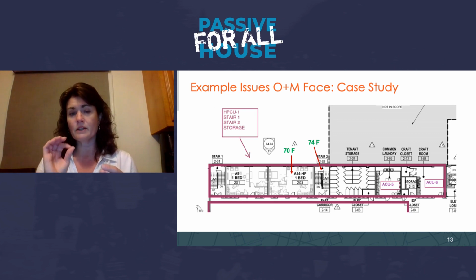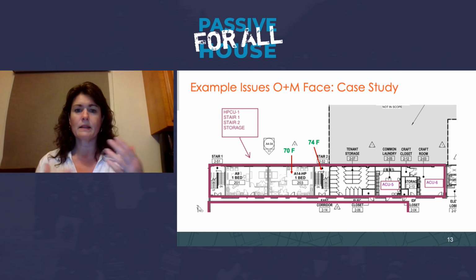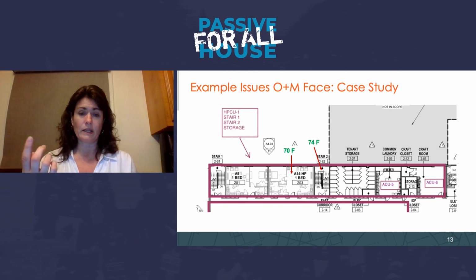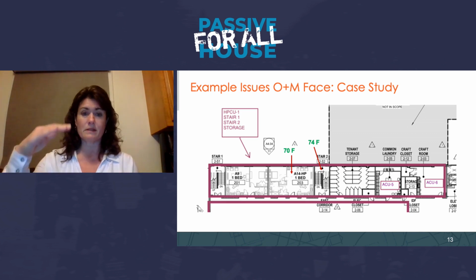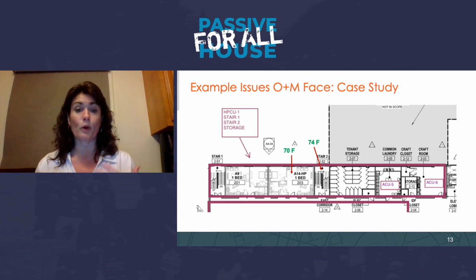Initially, the contractor set this up the way it was intended, but somehow it got altered or changed - when the system rebooted, the setting in the stairwell went to 74. The setting in the apartments was only 70, and they weren't calling for heat, but because the stairwell was calling for heat, they were overheating - their temperatures were going up into the mid and upper 70s.